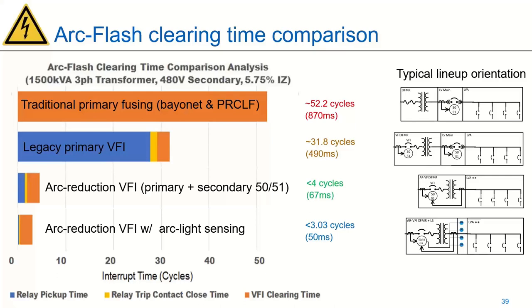Not only do you have the division of the ratio of the transformer that's going to lower that fault current on the primary, but you're also dividing again by the square root of three because of that delta. You're splitting up that load. So depending on your system, depending on the fuse coordination or the recloser coordination, one can be slightly faster or slower than the other.